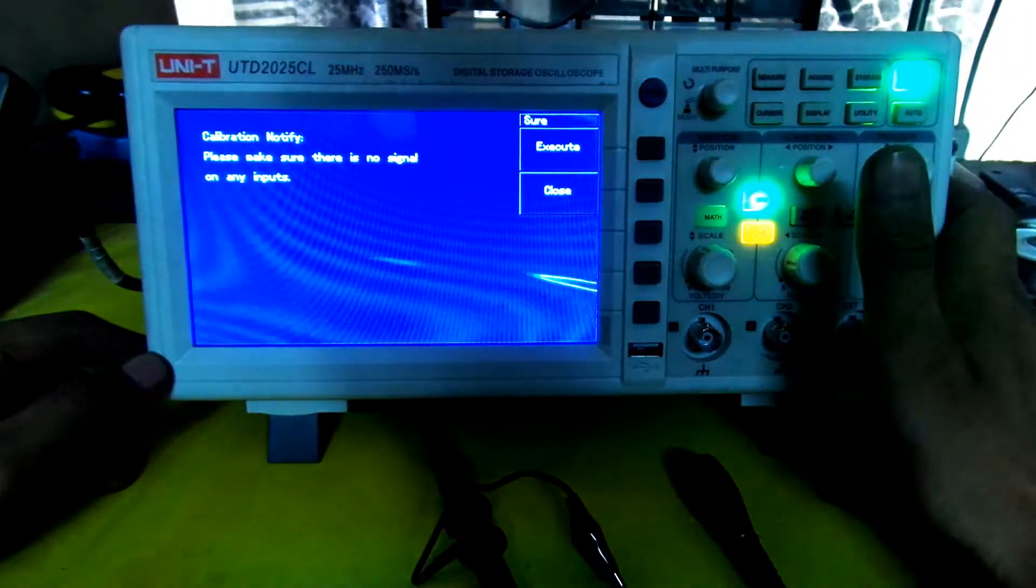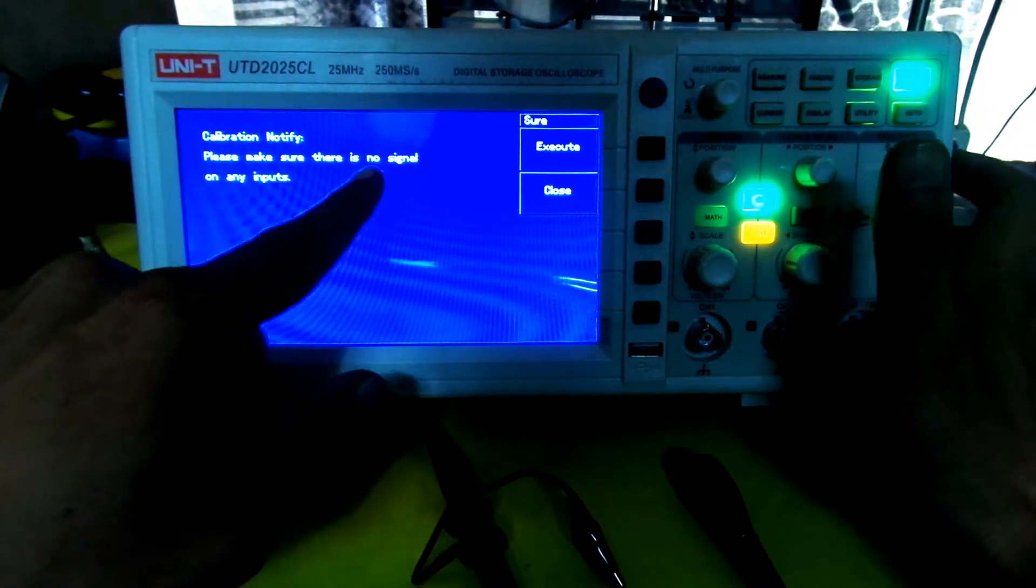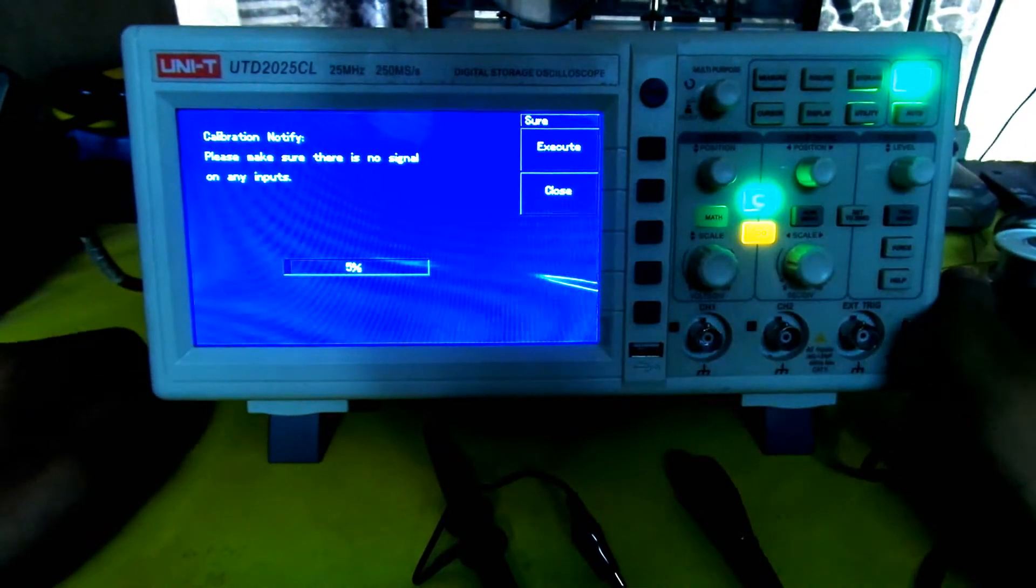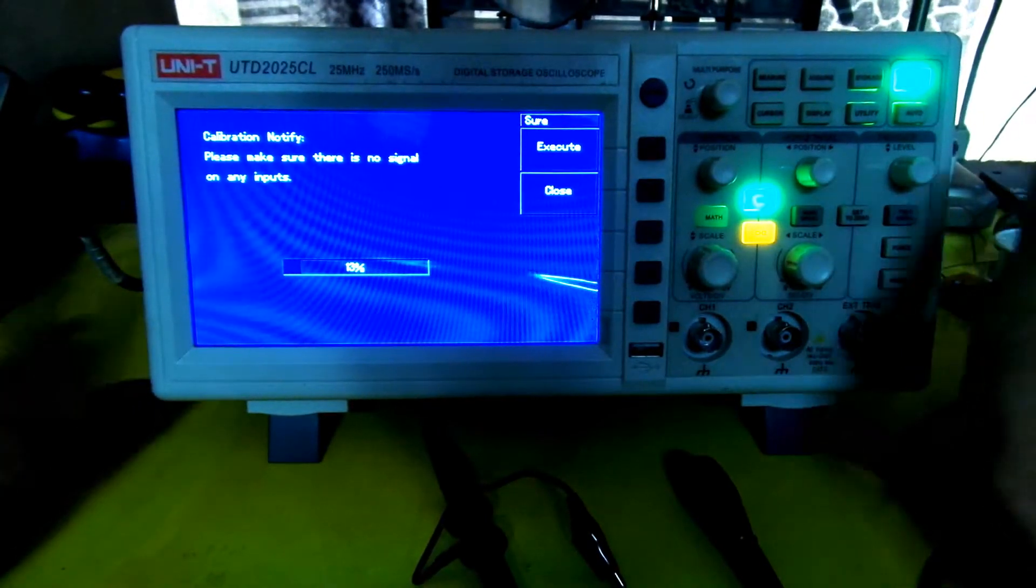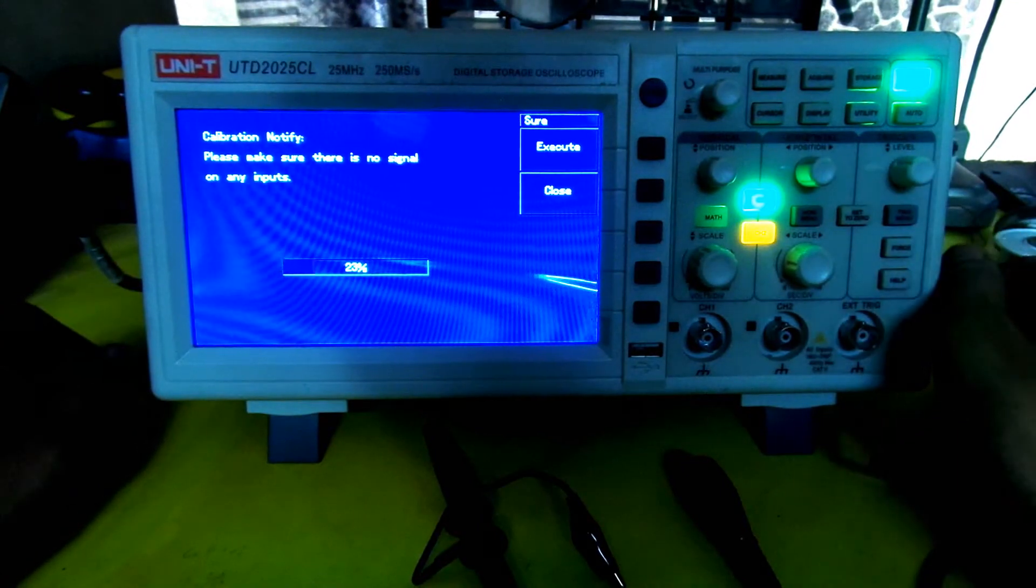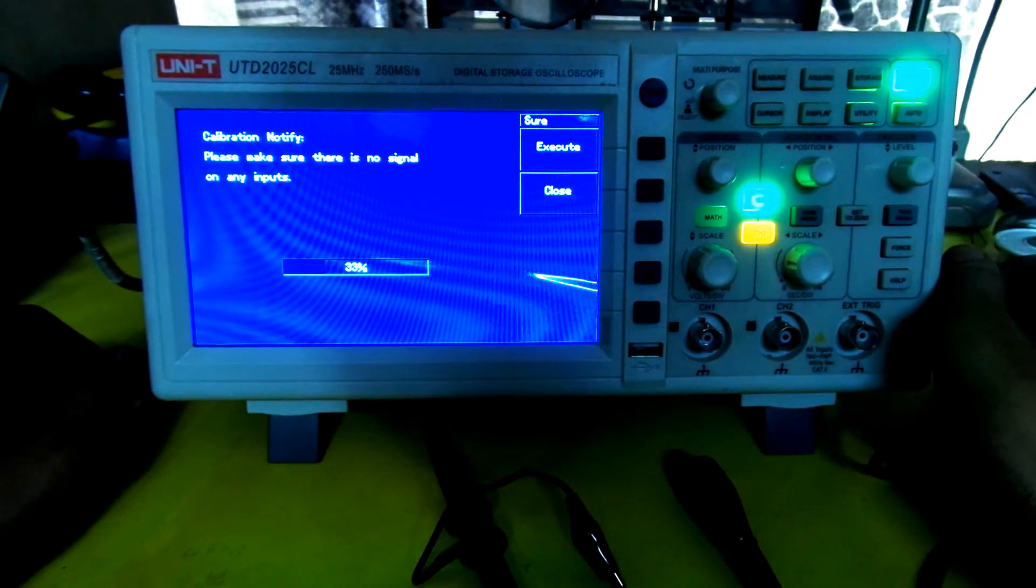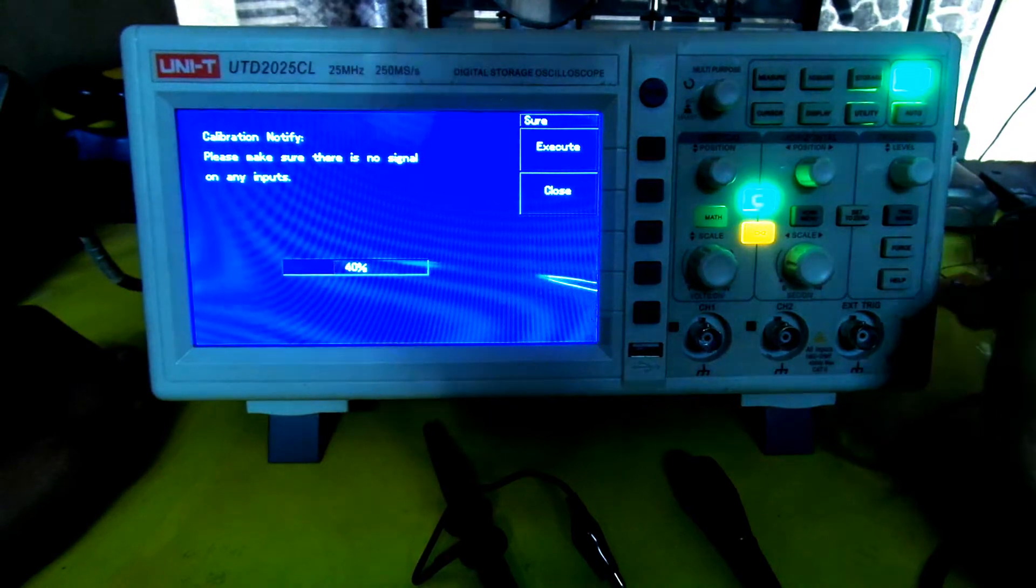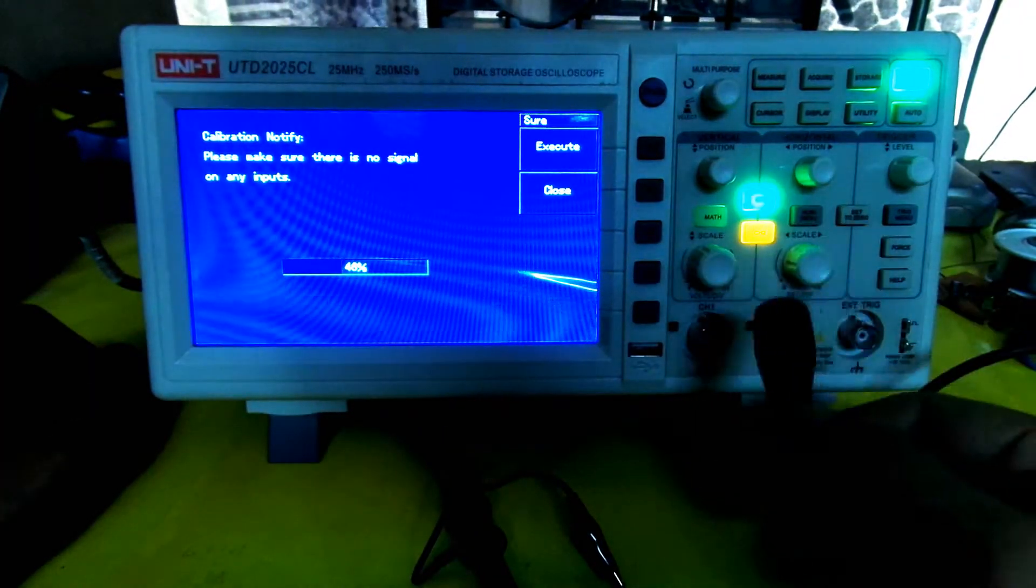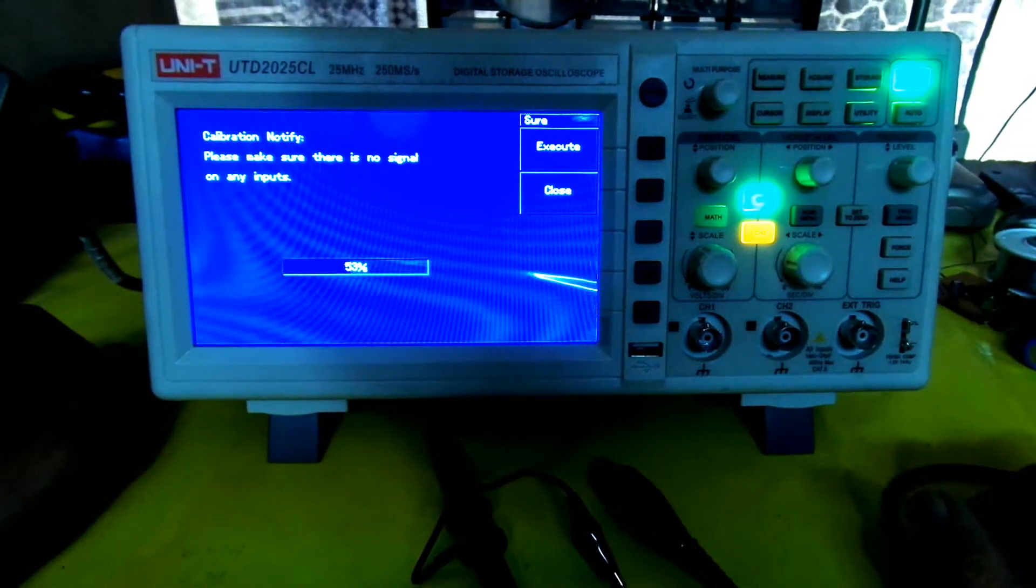We clicked on self-adjustment calibrating. It notifies: please make sure there is no signal on any input. You're going to execute that. It will automatically adjust things for you. I can hear clickings of the relays inside. Then you can plug the probe onto whichever channel you like. I'm going to plug it inside.